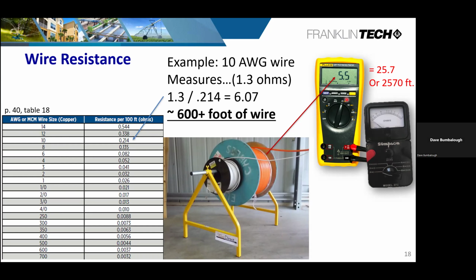But as I show you also in this picture, I'm getting 5.5 ohms. If I was to divide that out, it's equivalent to 2,570 foot. I know, no way that's on there. So that tells me right off the bat I've got something wrong with my wire. So it can also help you troubleshoot that there's a problem. And the misconception is, okay, it's brand new. Well, yeah, manufacturers make mistakes. We're human. Things can happen. I was recently at a job site where the wire was blemished. They identified it, and apparently whoever rolled it up didn't catch it, and it actually went out in the field. So things happen. This is just one way of checking and proving out what's going on with the system.